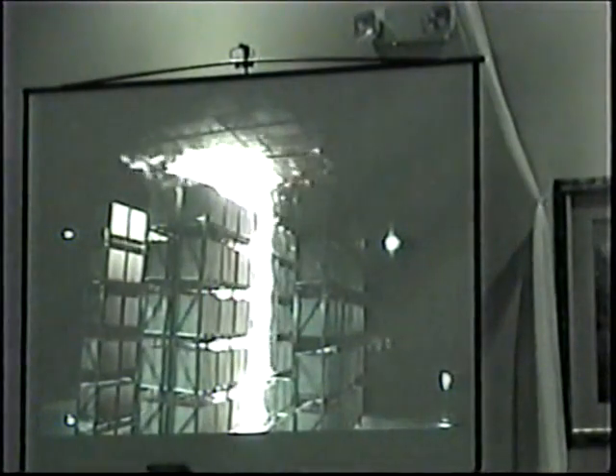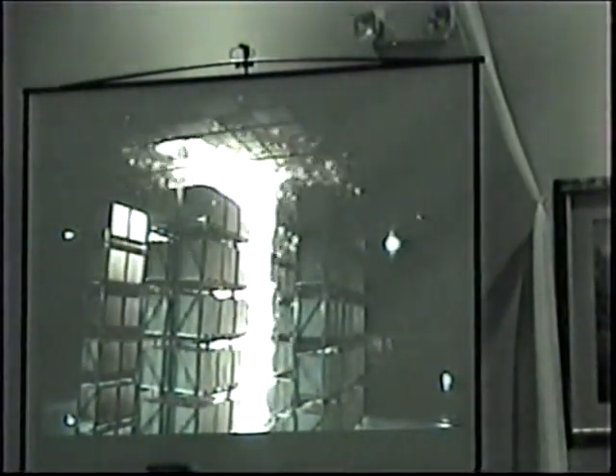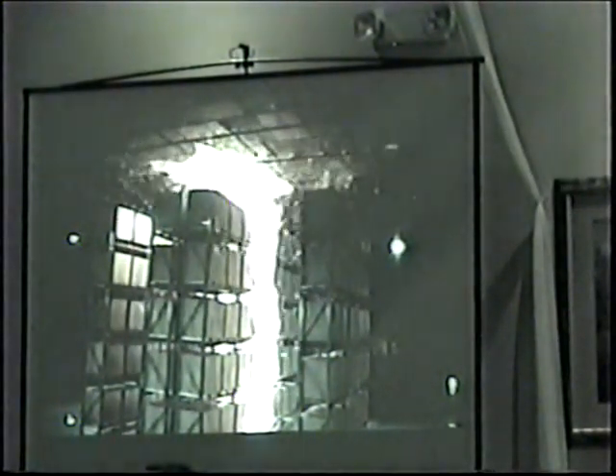5-foot clearance, so it's 30 feet of storage under a 35-foot ceiling. I think this is 25 or 27 seconds delay on the water delivery. If you listen close, you can hear the heads operating. And I think in this test, over that delay period, we operated 16 heads. And it works fine. You can watch it through sort of the lens.